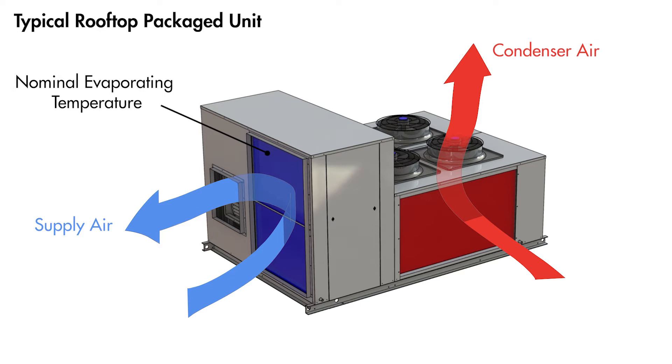In a cooling scenario the nominal evaporating temperature, which is the temperature of the refrigerant in the evaporator coil, is typically around seven degrees celsius. This allows conditioned air to be cooled down to approximately 12 degrees celsius.